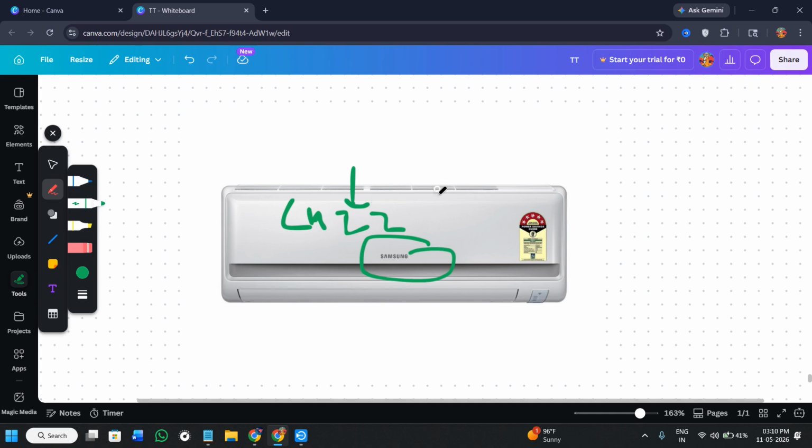actually work. So on the Samsung air conditioner, the C422 code is commonly linked to indoor or outdoor communication failures, sensor reading abnormalities, or sometimes it is relating to PCB or wiring interruptions. So this error often appears after voltage fluctuations or sudden shutdowns.